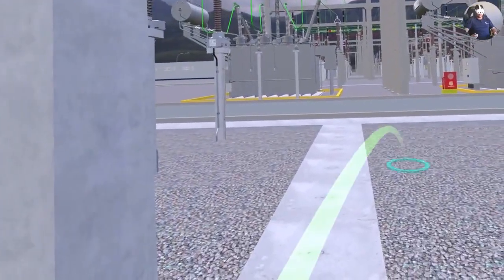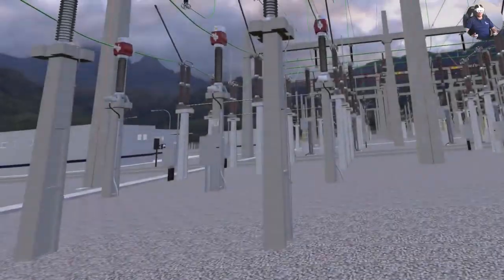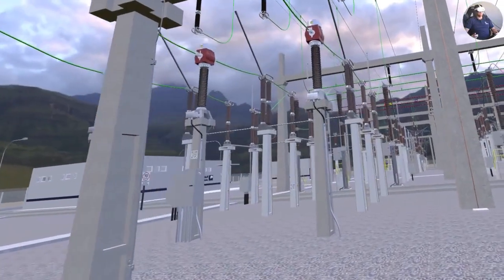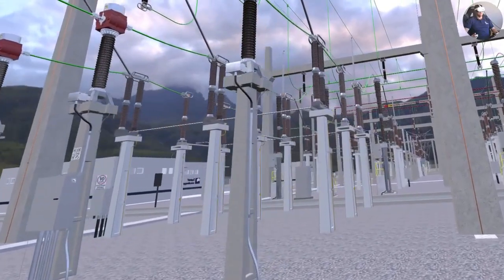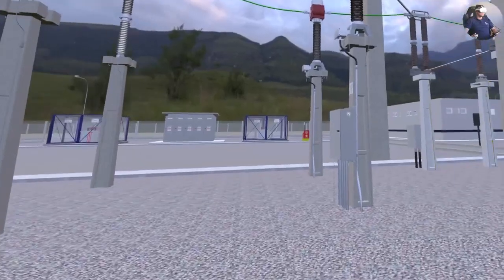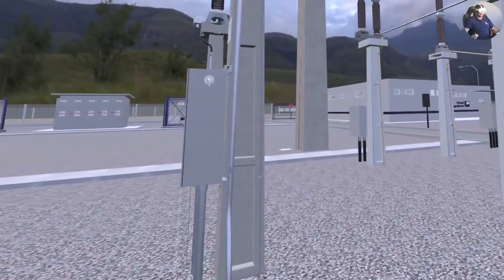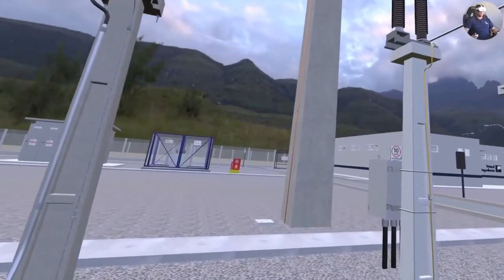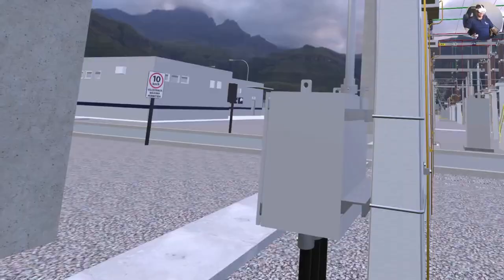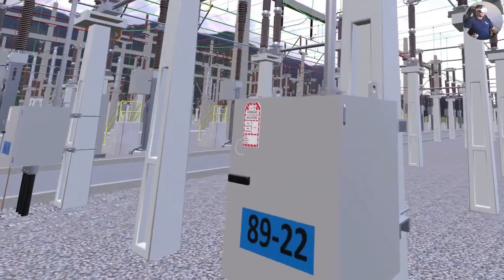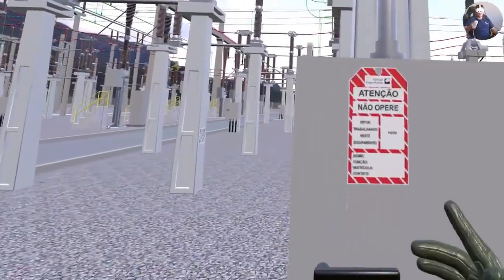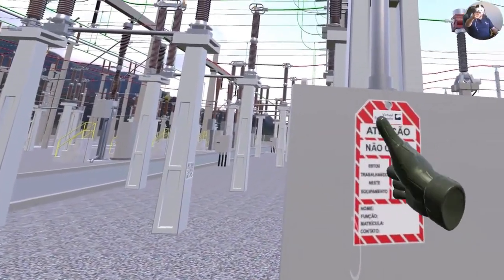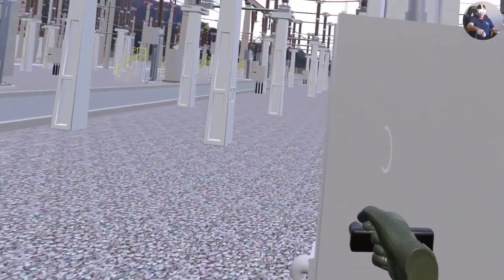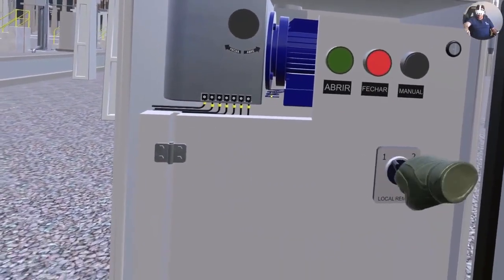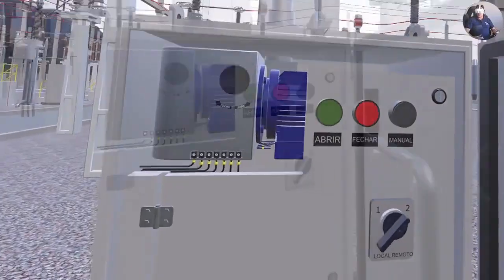Now let's carefully close the disconnectors right here in the connection module of the 230 sector. Let's close this one. We put a lockout here, right, guys? So the maintenance team has already removed the temporary grounds, right? And here we're going to remove the lockouts, right? So here we have a safety tag. We're going to remove this tag here, take it here, put it here. We switch this key here to local. We're going to switch it back to remote, right? Let's close the panel.